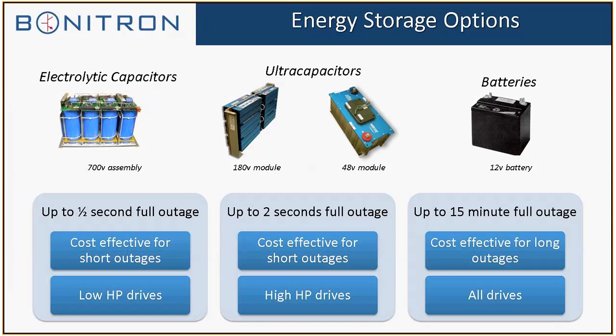Three types of energy storage, some information about them. We provide energy storage in modules, so when we do a module quote, we can provide loose ultracapacitors as long as you have the integration capabilities to wire them. We'll provide wiring diagrams. It's pretty simple connectivity. You do need to know a little bit about what you're doing, so it's good to have an integrator involved. We package the capacitors in the modules, 700 volt assemblies, and we'll run those in strings to be able to cover the required capacitance for the DC bus.